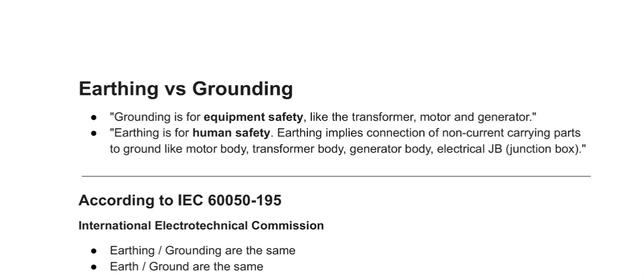So what is the reality? Let's discuss. The general thinking is that grounding is for equipment safety, like earthing the transformer neutral and the generator neutral. Earthing is for human safety, where we earth the equipment body, like motor body, transformer body, generator body, feeders, JBs, etc. So grounding is for equipment safety and earthing is for human safety.